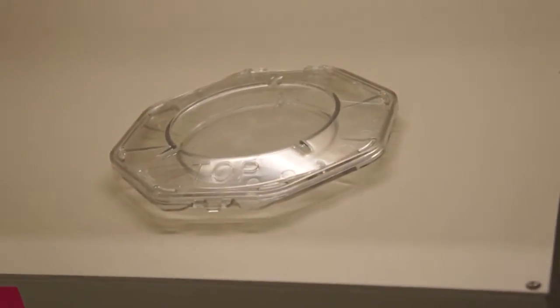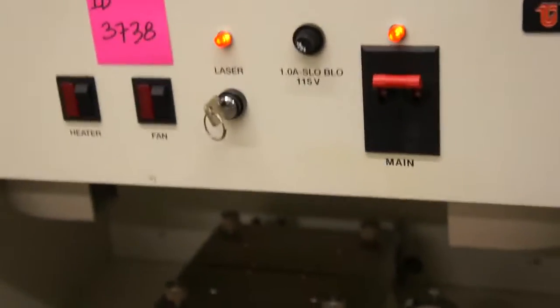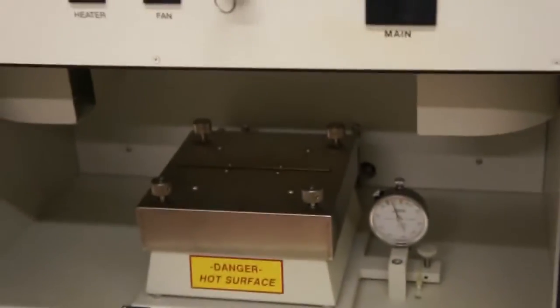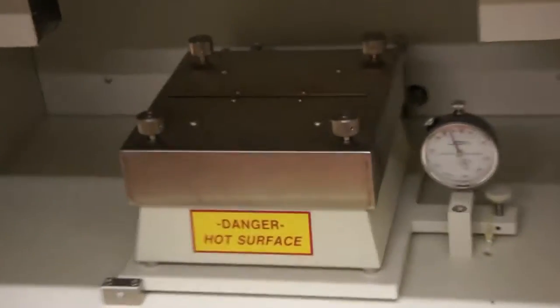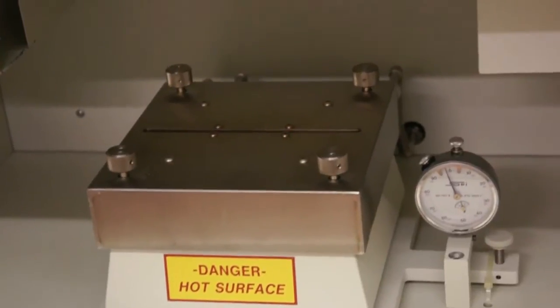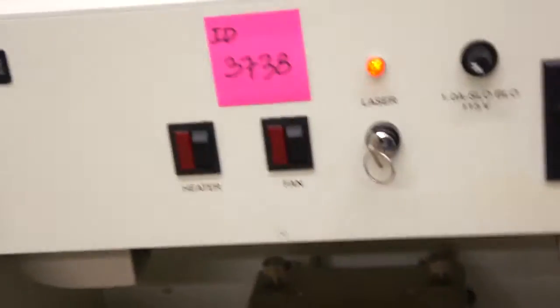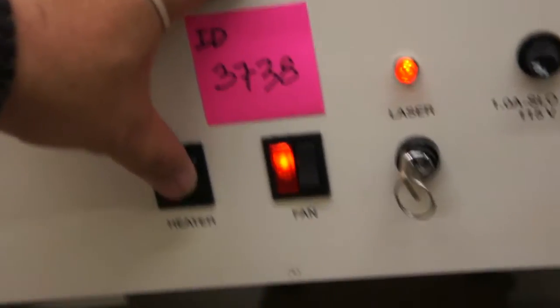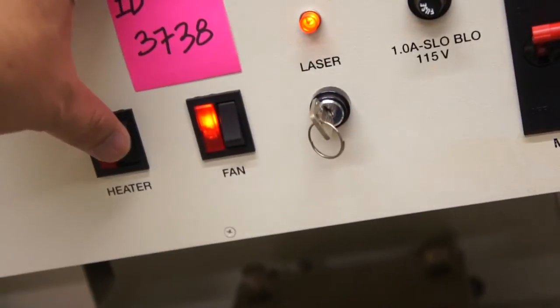So I had to change out the wafer to a test wafer that I normally run, and it's already installed. So as far as doing heated measurements, you like to put on the heater cover, and then also you want to make sure that your fan is running, and this keeps the heat from rising to the top chamber where the translation stage is.